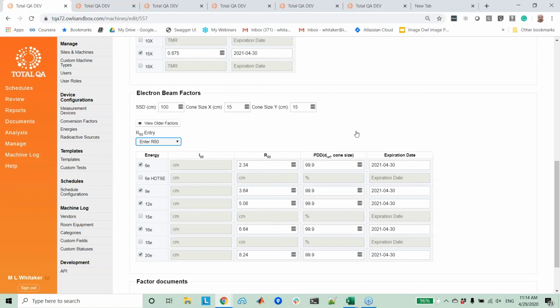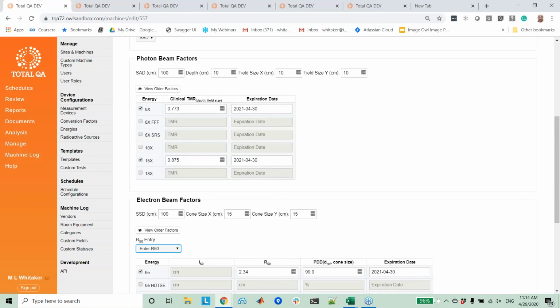As Ariel mentioned, this is one of those areas where we think there are some beneficial side effects in the rest of the software. If you've got a large organization, almost inevitably you've got some energies for certain machines that don't apply to any other machine. So the nice thing is, once you set this up with the energy in this machine, anywhere else in the software, even when setting up a monthly or a daily schedule where you need to set up energies, for photons all you're going to be able to choose from is 6x and 15x, because that's all this particular machine does. That simplifies a few things and prevents errors in different parts of the software.